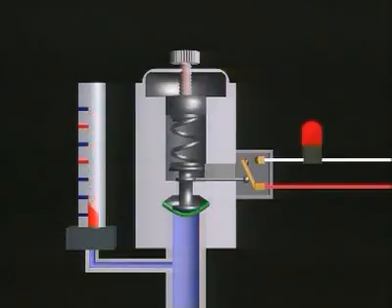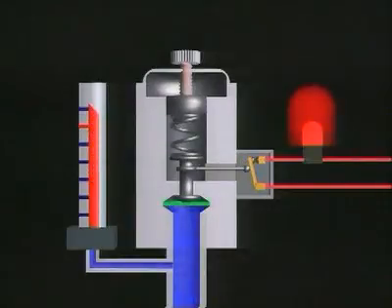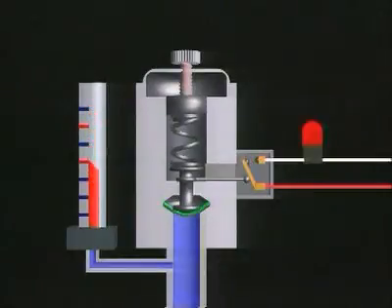If the pressure drops, the switch automatically opens again at a certain pressure. The difference between the switch on point and the switch off point is the hysteresis of the pressure switch. This varies according to the pressure range. The hysteresis is caused by the frictional resistance in the components of the switch. It is important to know the hysteresis of a switch because it switches at different points for rising or falling pressure.